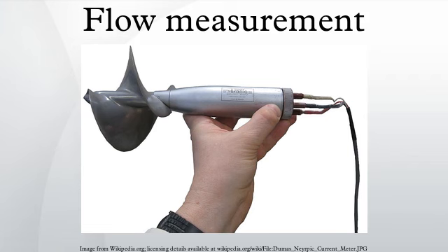Open channel flow measurement, level to flow. The level of the water is measured at a designated point behind a weir or in a hydraulic structure using various secondary devices. This depth is converted to a flow rate according to a theoretical formula of the form Q = KH^n, where Q is the flow rate, K is a constant, H is the water level, and n is an exponent which varies with the device used. Or it is converted according to empirically derived level-flow data points. The flow rate can then be integrated over time into volumetric flow.